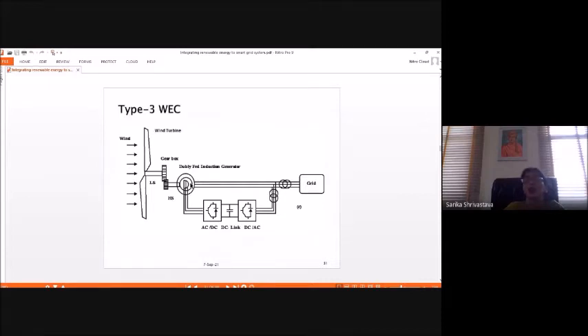It has two converters. There are two paths to supply: one is connected with the stator, the outer part, which is carrying the three-phase winding. It is connected to the grid, and an alternate path is through the rotor. That's why it is able to work over a broader range of speed. So one converter is here, another here, and both are coupled through a DC link.